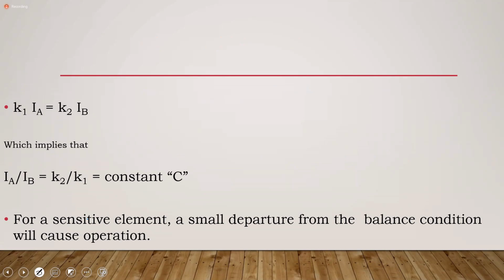Which means that the ratio of the two currents would be constant. Or in other words, that would establish balance. So A over B is equal to some constant. Now, once you have a departure from this balance condition, it means that you need to operate. Going back to the original principle, the relay has these predetermined conditions for operation. So you have the balance, IA over IB is a constant. Once there's deviation, it means that you need to operate.